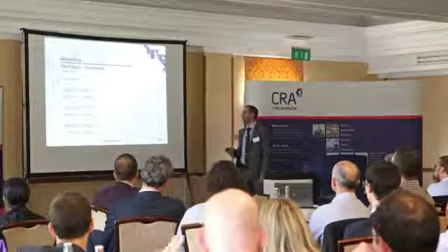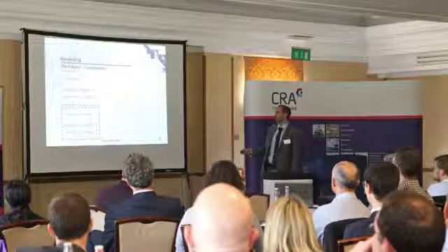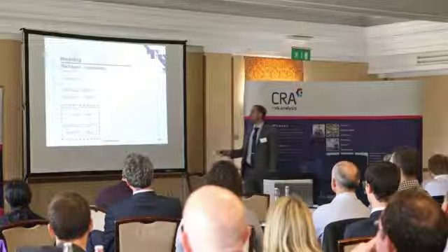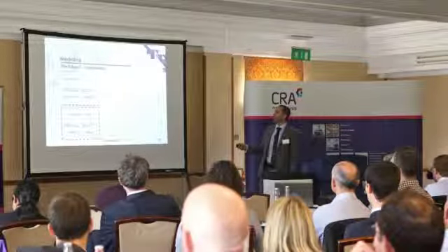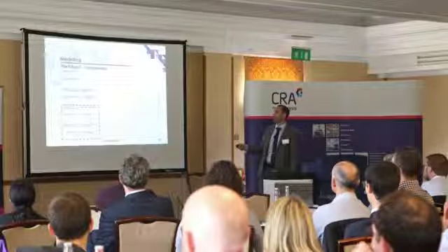So one of the ideas in my head, which I'm putting into practice at the moment, is independent failure. So you have your regular random failure, a seismic event occurs, and you now include a component-based seismic event, and a building-based seismic event as well. The key thing is that this is the conditional failure probability of your component or your building, assuming if your building fails, your component fails. That comes in, and that, if you like, goes under the logic of random failure.